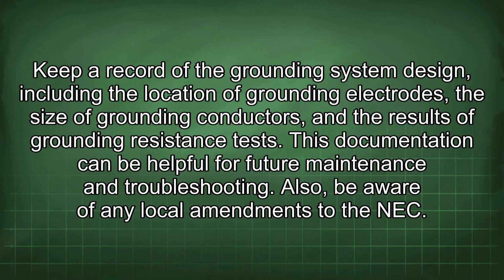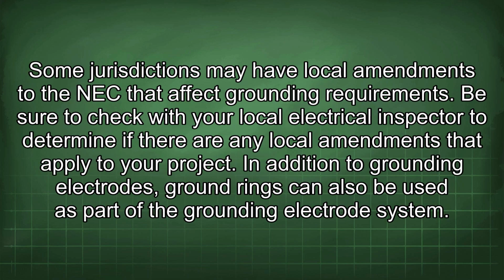Also, be aware of any local amendments to the NEC. Some jurisdictions may have local amendments to the NEC that affect grounding requirements. Be sure to check with your local electrical inspector to determine if there are any local amendments that apply to your project. In addition to grounding electrodes, ground rings can also be used as part of the grounding electrode system.